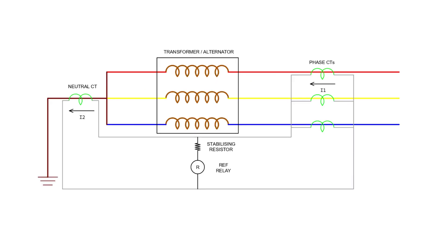While differential protection covers about 80% of the winding, REF handles the remaining protection. It protects the transformer winding from earth faults, specifically in the zone between the transformer star-side winding and its earth-neutral terminal. These protections are crucial for detecting imbalances and earth faults in transformers.